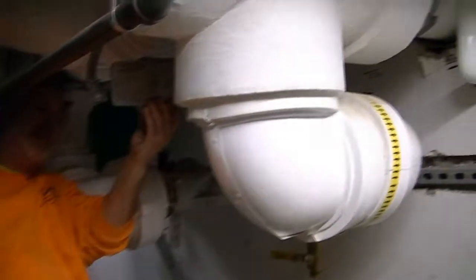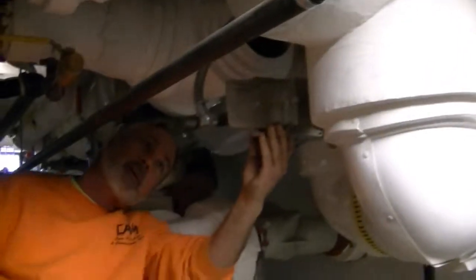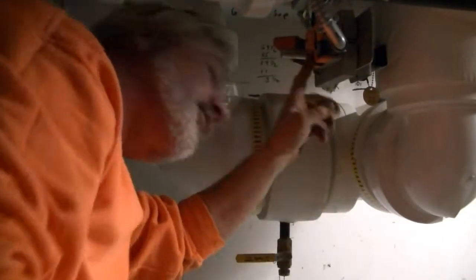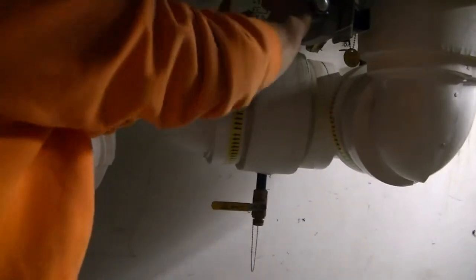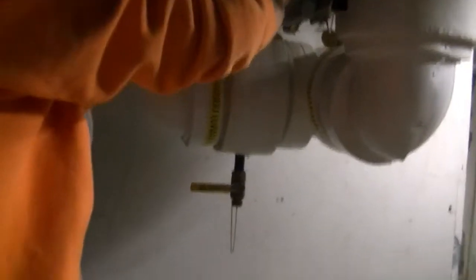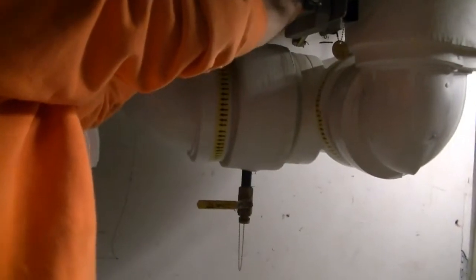There's a release on the side of the valve. You push the release in, and then you can stroke the valves, but you have to do them both at once. You can't do one and not the other. Yeah, there's two actuators, so you kind of need three hands. You need two guys to do it. Each of you would push the button. One guy would push the two buttons down, the other guy would stroke the valves.